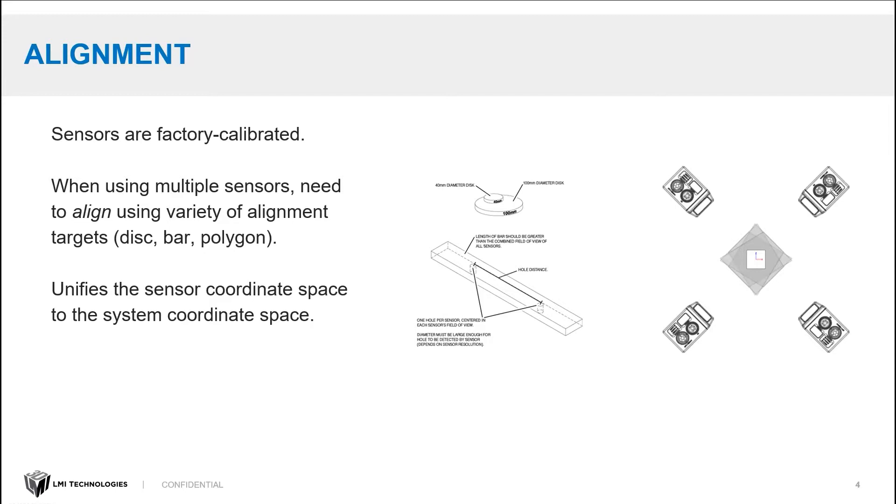But when you use multiple sensors, there is a need to align your sensors using some kind of alignment target, a disk, bar, polygon. There's a bunch of options available. And what the alignment does is tell all the sensors where the other sensors are so they can combine their scan data.